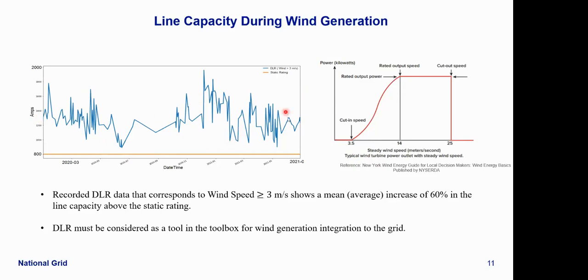And this DLR is actually giving me a 60% increase in line capacity. This is a huge number that we're missing. If I only go with the static rating and connect wind generation to this line, I have to keep curtailing that wind because it's going to continue to exceed that static rating. But if I go with the DLR for a typical wind speed curve, I can accommodate an additional 60% on that line without overloading it.